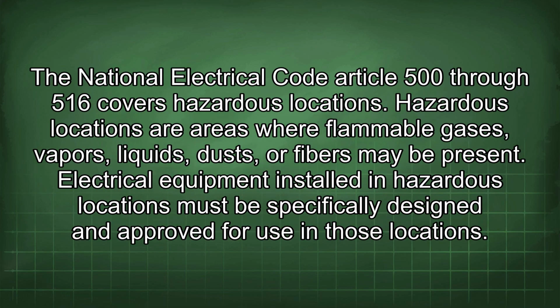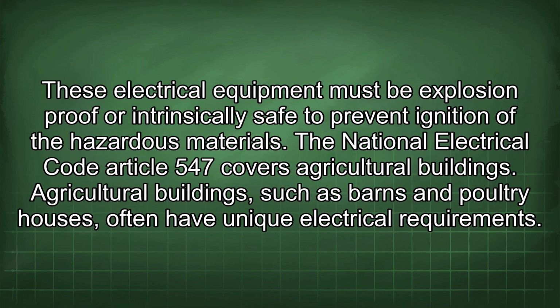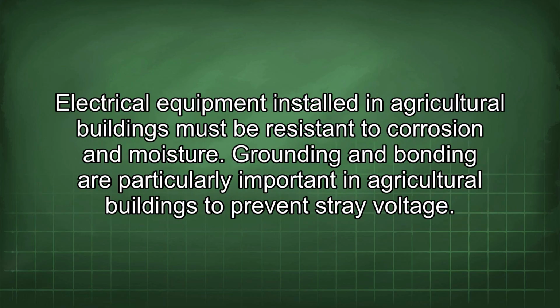The National Electrical Code Articles 500 through 516 cover hazardous locations. Hazardous locations are areas where flammable gases, vapors, liquids, dust, or fibers may be present. Electrical equipment installed in hazardous locations must be specifically designed and approved for use in those locations. This electrical equipment must be explosion-proof or intrinsically safe to prevent ignition of the hazardous materials. The National Electrical Code Article 547 covers agricultural buildings. Agricultural buildings, such as barns and poultry houses, often have unique electrical requirements. Electrical equipment installed in agricultural buildings must be resistant to corrosion and moisture. Grounding and bonding are particularly important in agricultural buildings to prevent stray voltage.